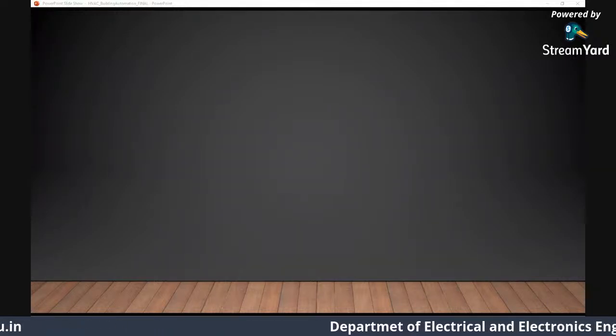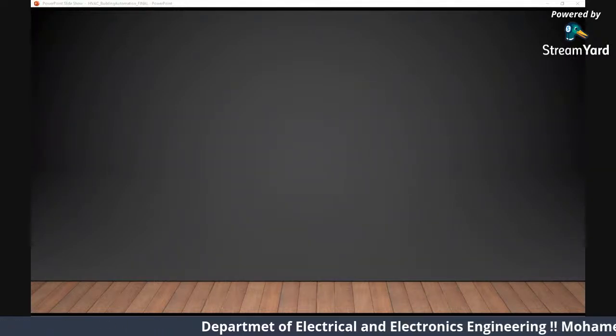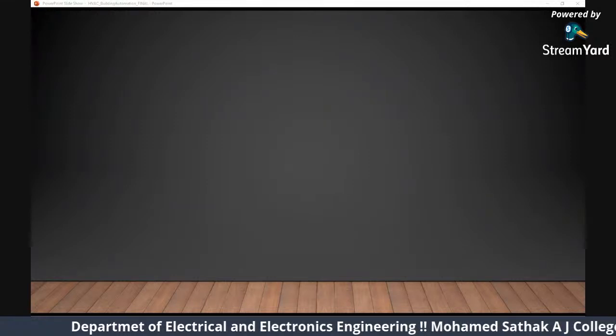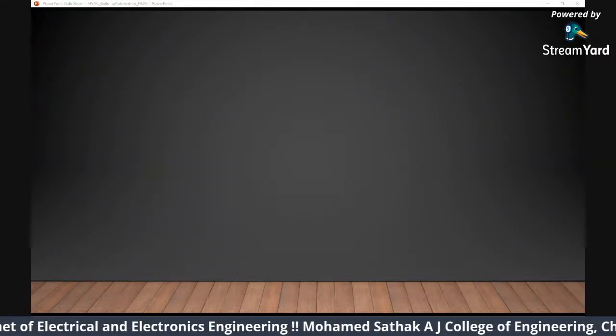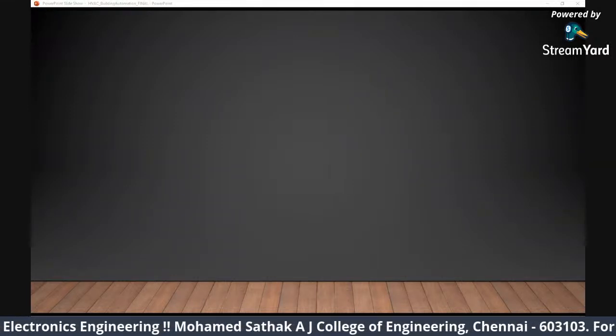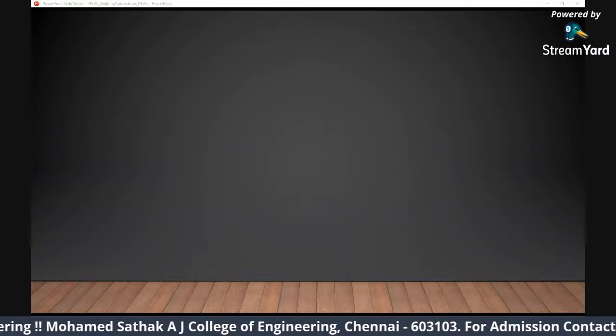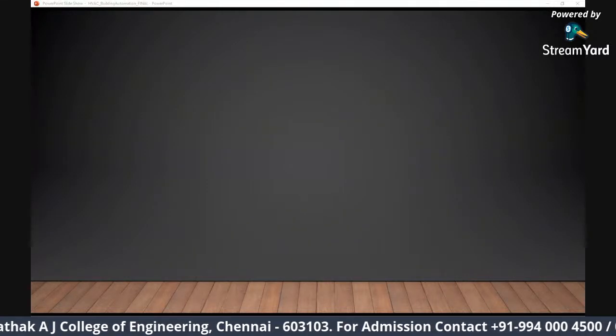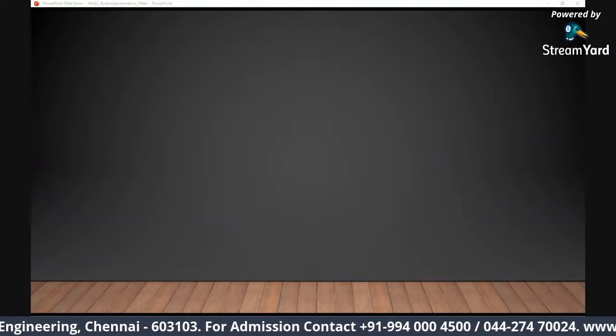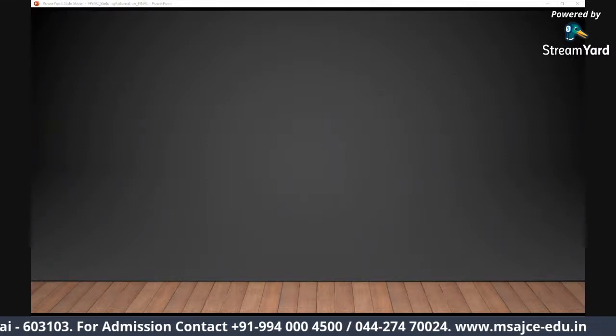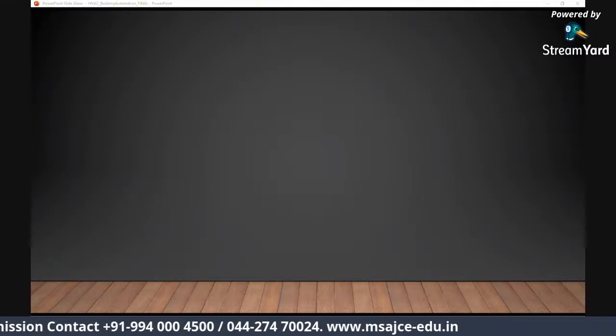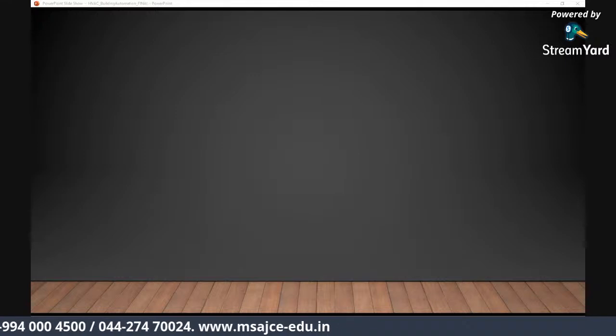Let's say 8 doors are your exit and entry, and 2 doors are for your data centers, or where your high expense equipment is kept. Those 2 doors will fail closed during power loss, and the rest of the 8 doors will fail open during power loss. That's how they program it. It's again based upon the client. He will tell which door is to fail open and which door is to fail closed during power loss. This applies to valves and dampers as well.